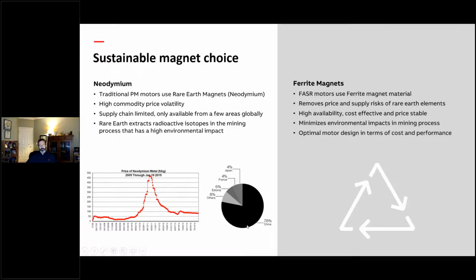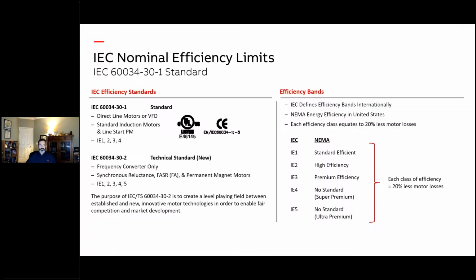This just shows you where the neodymium boron iron magnets come from, 78% out of China and a few other parts of the world. That's why, from a magnet technology standpoint, a lot of companies, even EC motors, are looking at redesigning to ferrites for the same reason. It's something to look for in a motor design, because if you're still using rare earth magnets in these low horsepower motors, you might get into a situation where, because of commodity or supply chain issues, you can't get the motor. So that's why this design uses ferrites or ceramic magnet material.